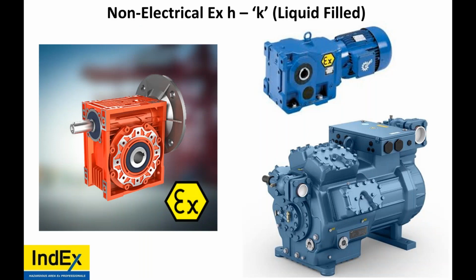Let's talk about EXH, or as it used to be known, specifically for liquid filled, EXK. This has now changed within the last few years. A device will no longer be labeled as EXK, it'll be EXH. So if you had an EXD motor and you had a gearbox, this would be EXDH or DBH or DCH. So what do we have here? Gearboxes are the most common filled one. Liquid filled or liquid immersion device for EXK. Another one is compressors.